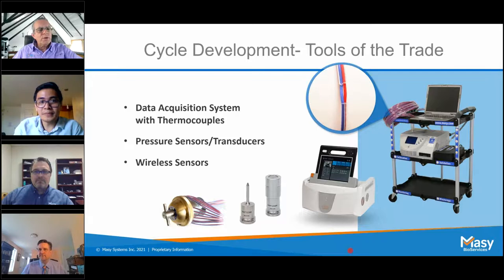Sure, thank you. On the pressure transducers, typically they're used in the EU regulated sterilization. Some companies look at temperature pressure through the correlation data, right? Definitely consider the temperature compensation specifications on the transducer when you get them, because most transducers are designed to go up to 50 degrees. You're going to be putting them on a steam line that's going to go up to 120 something degrees. It'll totally throw you off. So consider that definitely when you order them. All right, thank you.